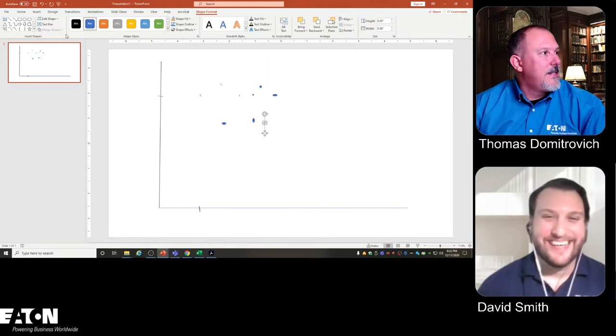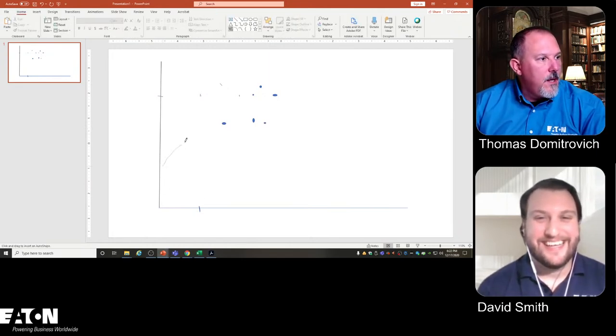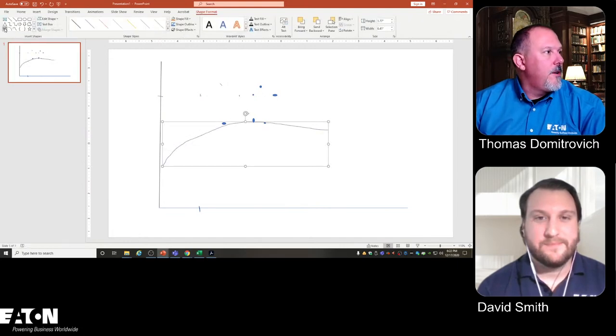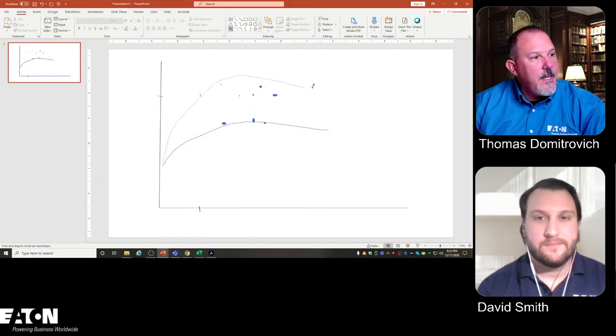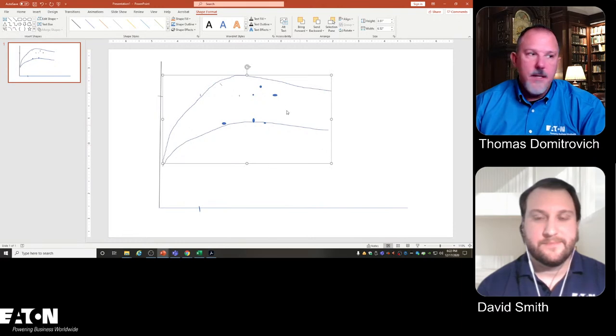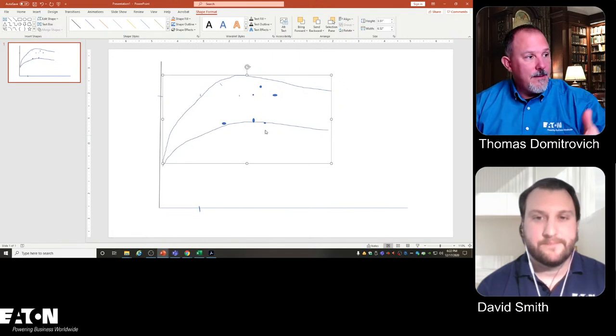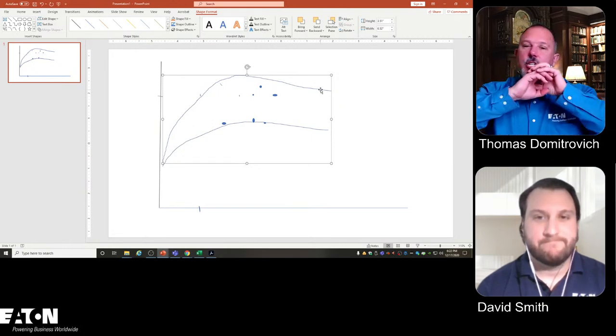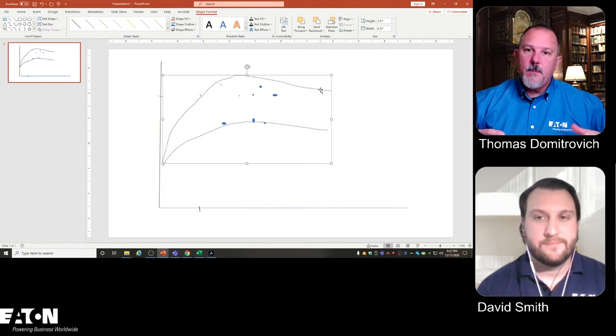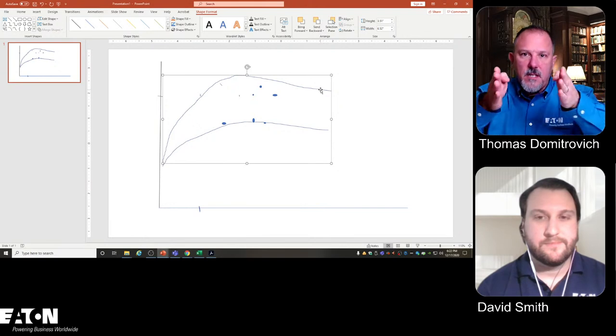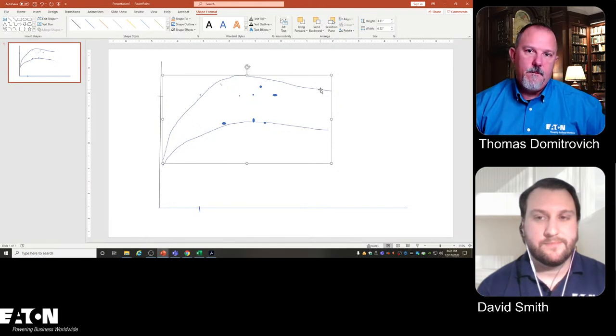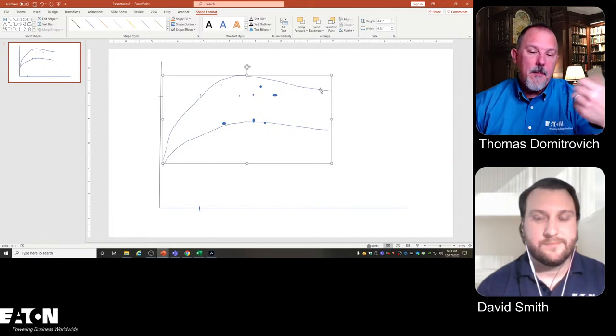So what he does is he says, all right, I am going to draw a curve, and I'm going to take in these. And I'm going to draw another curve, and I'm going to take in all of these. And then he develops an equation. He developed an equation to calculate those values of arcing currents that were down here and those values of arcing currents up here. And what do you call those? Your minimum and maximum arcing currents. So he has this huge equation, which is based upon all the different parameters that he's measured, the configurations of the bus, the distance between the electrodes and all that good stuff. And he has all of this data. And then he developed two equations for arcing currents to get him a minimum and a maximum.